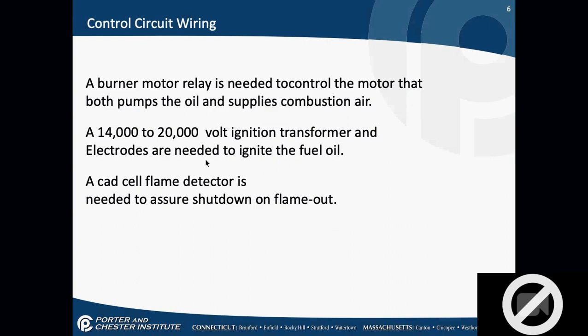Okay. We have to have a burner motor relay that's needed to control the motor that both pumps the oil and supplies the combustion air. We have to have a 14,000 to a 20,000 volt ignition transformer. We have to have electrodes to ignite the fuel oil. We have to have a cad cell flame detector, which we're going to talk about as we go through the rest of this course, to ensure flame. Okay, we want to shut down the motor. We want to shut down the oil feed if the flame goes out.